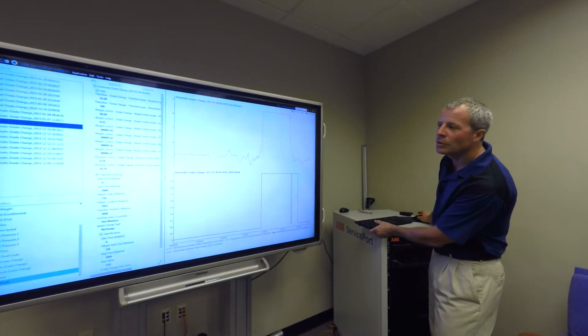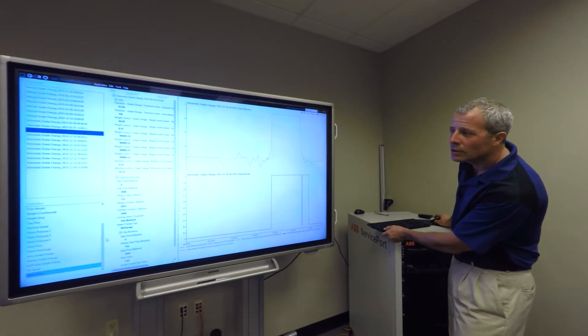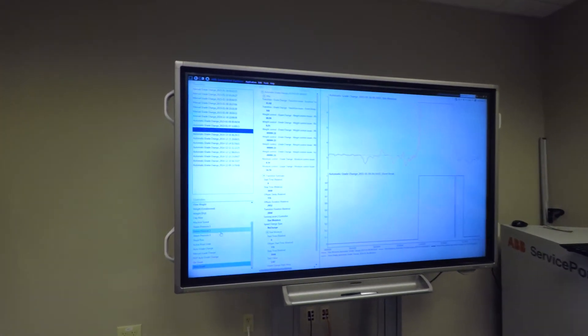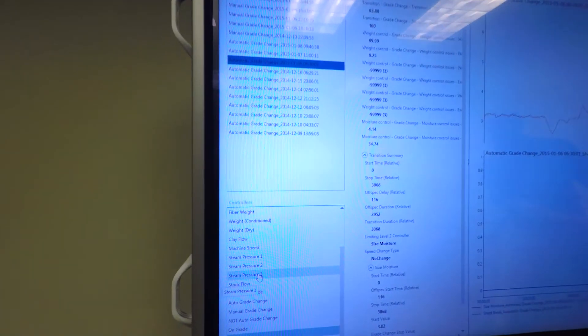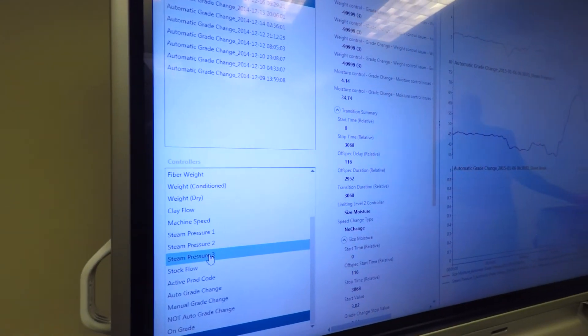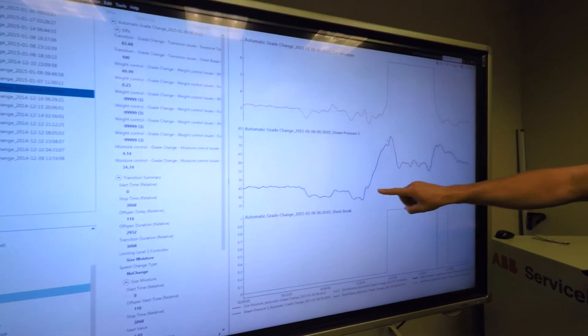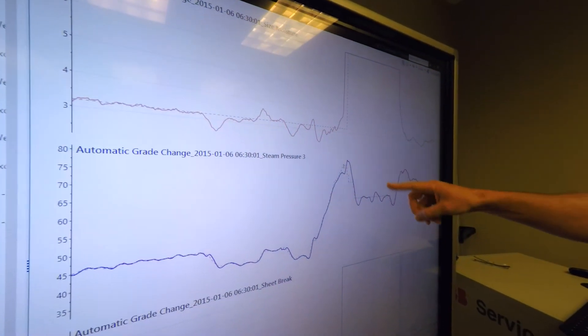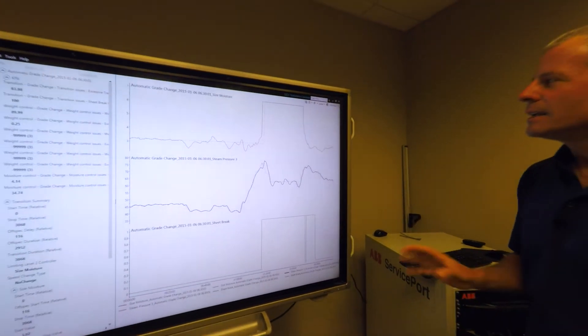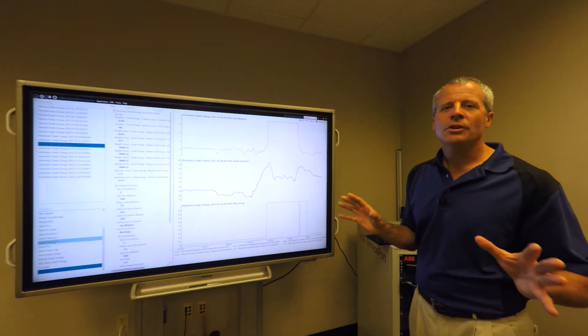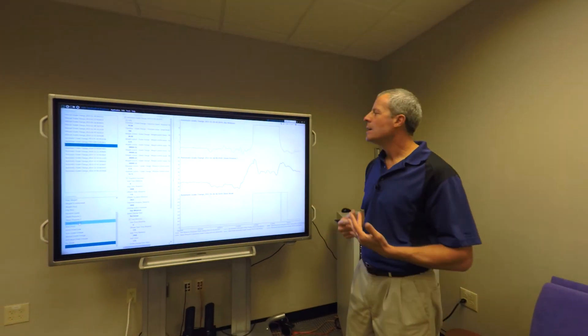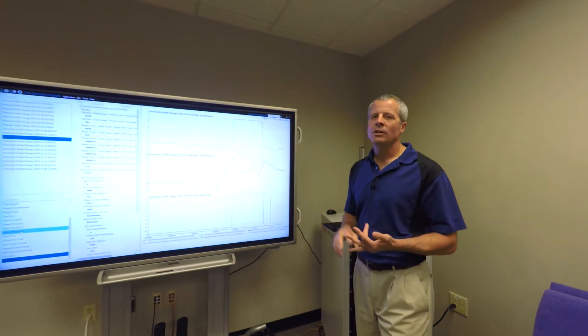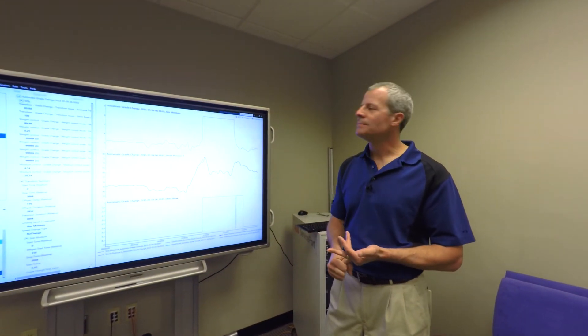We can also take a quick look at the steam pressure. In addition to the moisture, let's look at the steam. Here we can look at the steam pressure where we added steam. Some steam was taken off during the sheet break. This gives you the visualization of the grade change. It gives you a really quick way to identify what are the limiting factors of a transition.